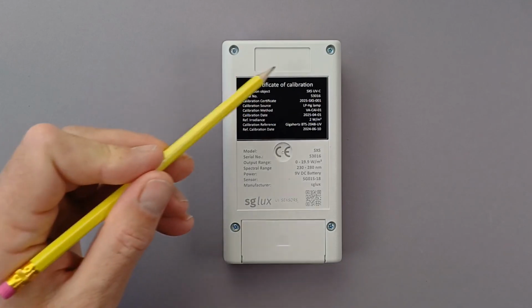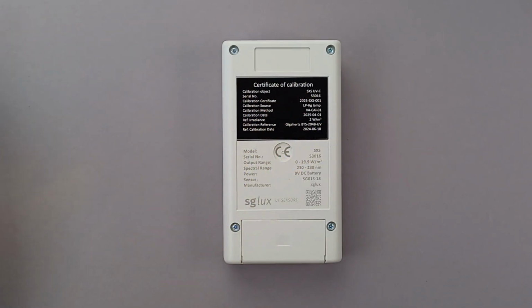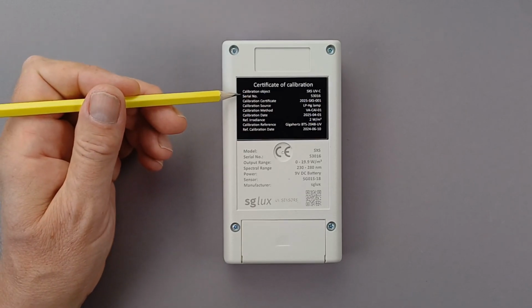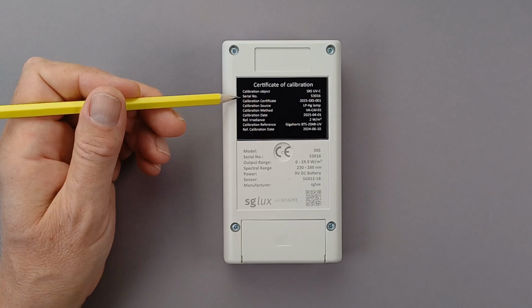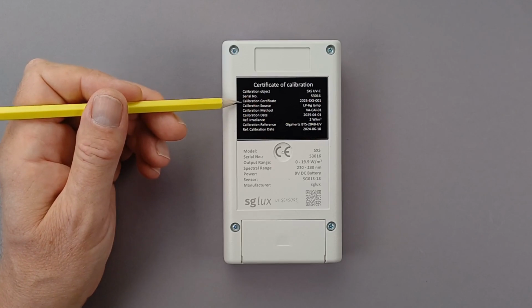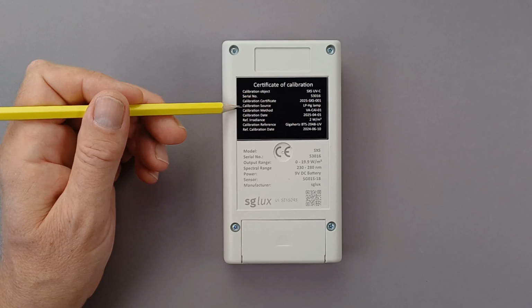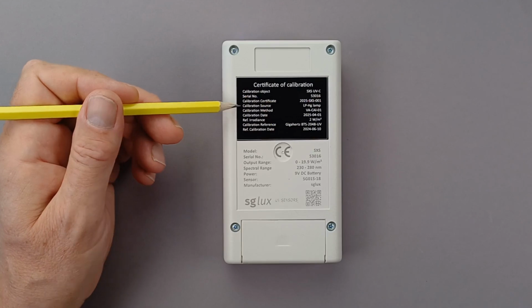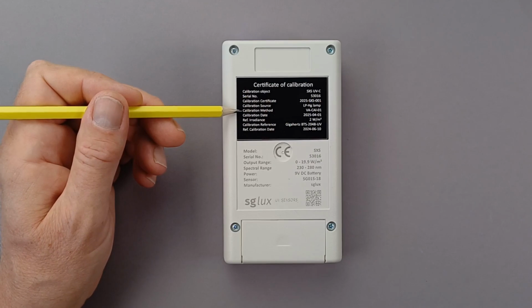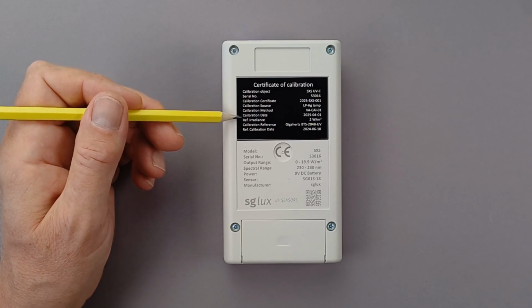The calibration certificate is located on the back and contains the following information: the calibration object, i.e. the description of the device, its serial number, and the number of the calibration certificate. Below this is the information on which source was used for calibration, in this case a low-pressure UVC tube. It should be emphasized that the device's measurement value is only correct if it is measured using the calibration source specified here. This makes it all the more important to carefully configure the device to the user's requirements, as mentioned above. The calibration method refers to the procedure manual we use to perform the calibration. The irradiance at which the calibration was performed is indicated after the calibration date.